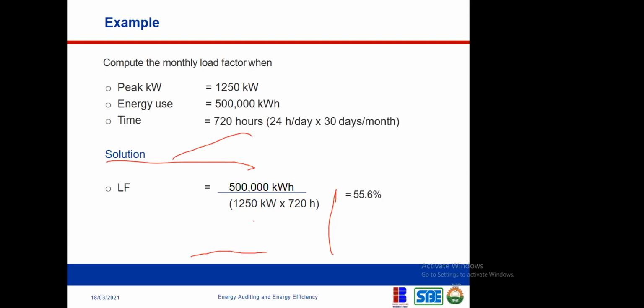55.6%. So out of the 100% capacity that you have, you're only using 55.6%, which is not bad. It becomes bad when it goes below 30%. It becomes very bad when it goes below 30%. So 55.6% is not bad. Now I'm speaking if you're using a generator. Your generator becomes highly inefficient and wasteful when you're running it under a 30% load factor. So I hope that makes sense.